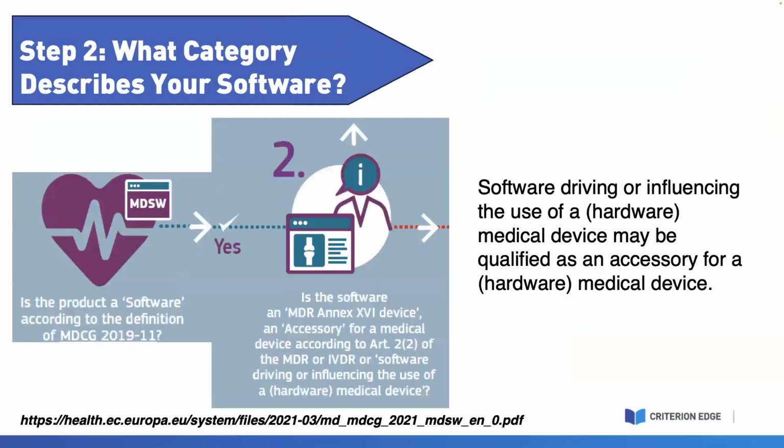So if it's software driving or influencing the use of a device, that's where the software is intended to drive or influence the hardware, but it does not have or perform a medical purpose on its own, and it doesn't create information on its own for one of those medical purposes. So the software can be limited to things like operating or modifying through some sort of an interface, or supplying output directly related to the hardware functioning of that device under the MDR.